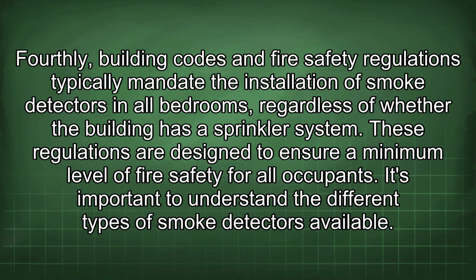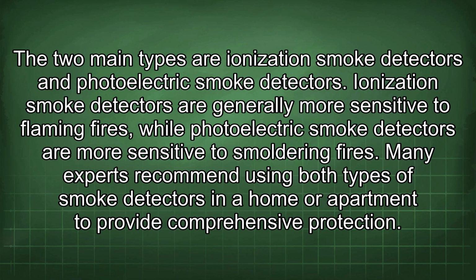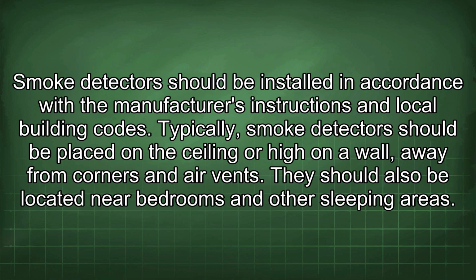It's important to understand the different types of smoke detectors available. The two main types are ionization smoke detectors and photoelectric smoke detectors. Ionization smoke detectors are generally more sensitive to flaming fires, while photoelectric smoke detectors are more sensitive to smoldering fires. Many experts recommend using both types of smoke detectors in a home or apartment to provide comprehensive protection. Smoke detectors should be installed in accordance with the manufacturer's instructions and local building codes. Typically, smoke detectors should be placed on the ceiling or high on a wall, away from corners and air vents. They should also be located near bedrooms and other sleeping areas.